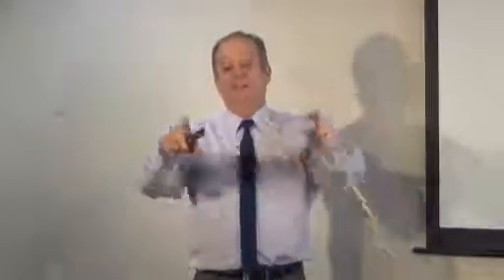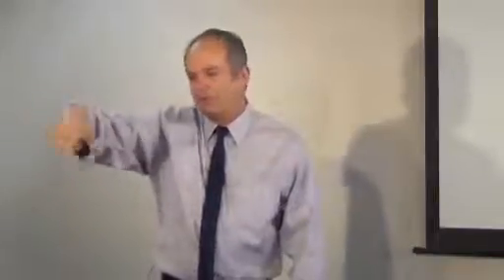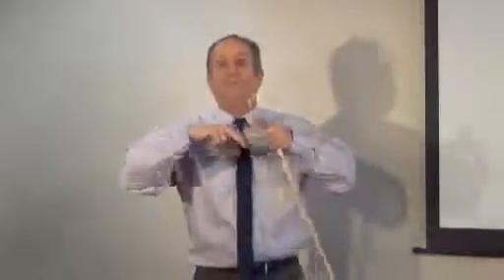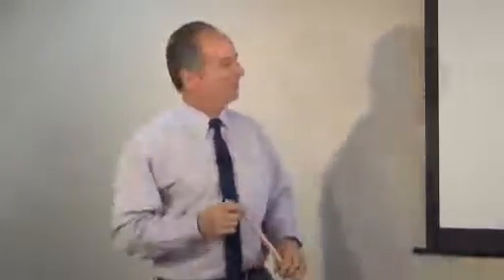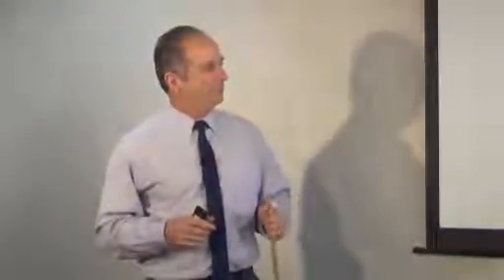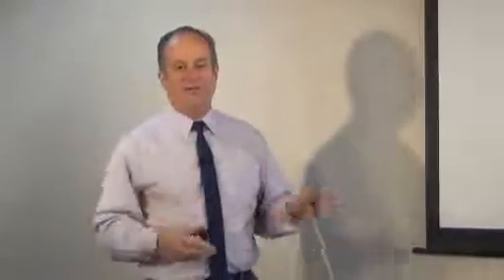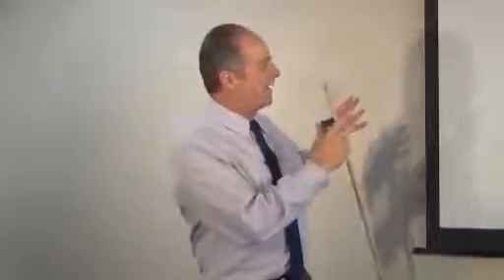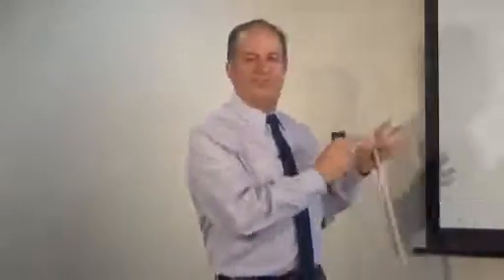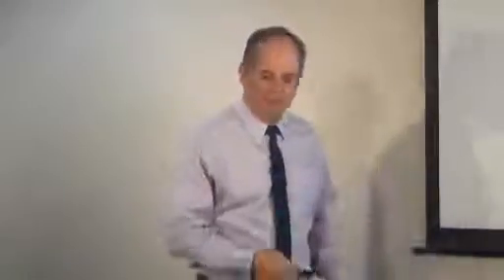And if there's fused laterals coming off the feeder, then just that lateral fuse will melt and just those customers are out of service. If it's a main feeder that this happens to, then the whole feeder goes out with the recloser. So it just depends. So I'm just saying there's reclosing and there is tripping. And you'll learn more about this in distribution courses that we offer. So this is basically the gist of a recloser on the distribution.